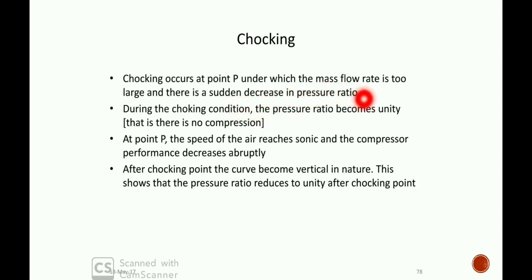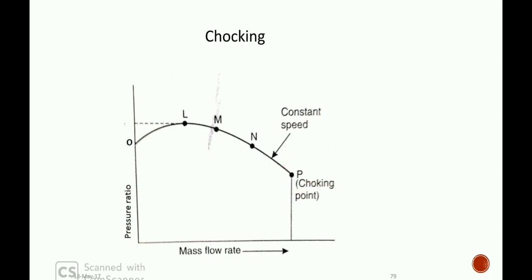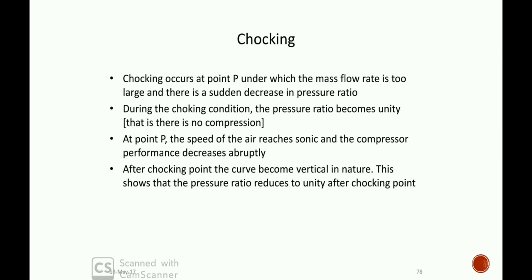During the choking condition, the pressure ratio becomes unity — that is, there is no more compression taking place. At point P, the speed of the air reaches sonic speed and the compressor performance decreases. After the choking point, the curve becomes vertical, showing that the pressure ratio reduces to unity.